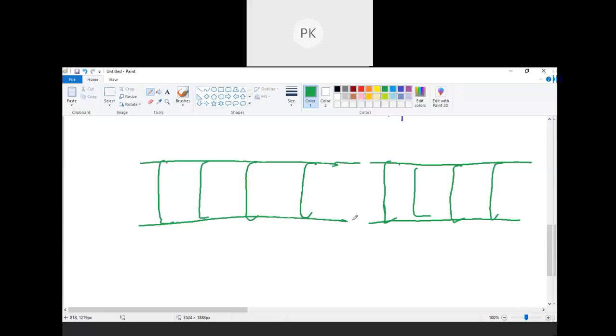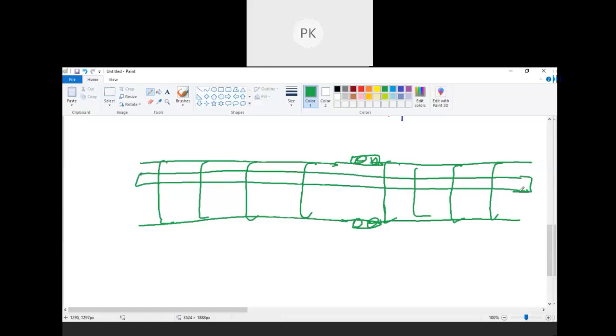Cable trays come in sections of 3 meters or something. Now every one of these sections is connected like this. They may be bolted or they may be welded. Now there is continuity, but still, what people do - some people have a practice of running a separate strip on the cable tray. This also reduces EMC problems. Okay, that is cable tray earthing.